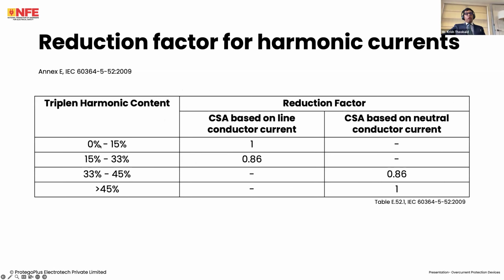Depending on the triplen harmonic content, we first decide whether we want to select the cable's size based on the line conductor or the neutral conductor. Once we decide that, between 0 to 33%, we decide on the basis of the line conductor current. Between 33 to 45, and in excess of 45, really in excess of 33%, the cable has to be selected on the basis of the neutral conductor current.